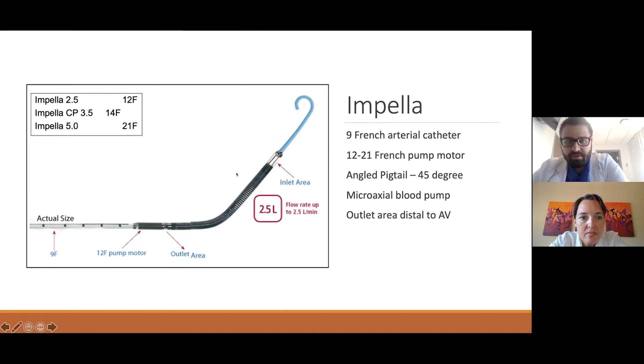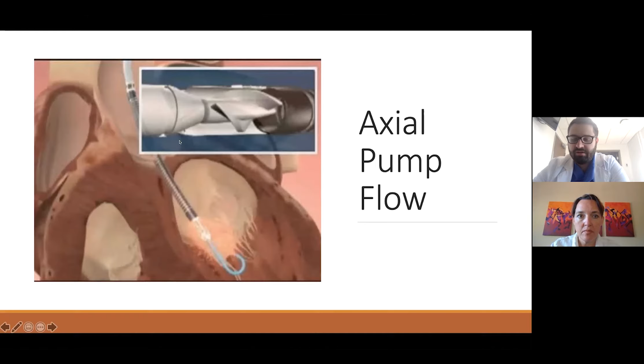So it's important to know that these are axial pump flow devices, where essentially there's a rotor here that spins around, and as that spins around, it creates a suction, and it basically sucks out the blood. And you can imagine if any sort of rotor spins around in your bloodstream, there's going to be some degree of hemolysis, and that's something that we definitely look for in our patients. But essentially, this is just a motor that spins around and creates that suction effect and gets the blood from point A, which is roughly here, to point B, which is out here, to help offload that work of the heart.